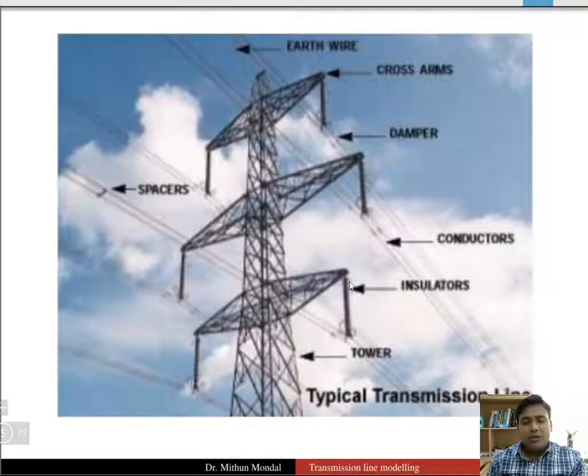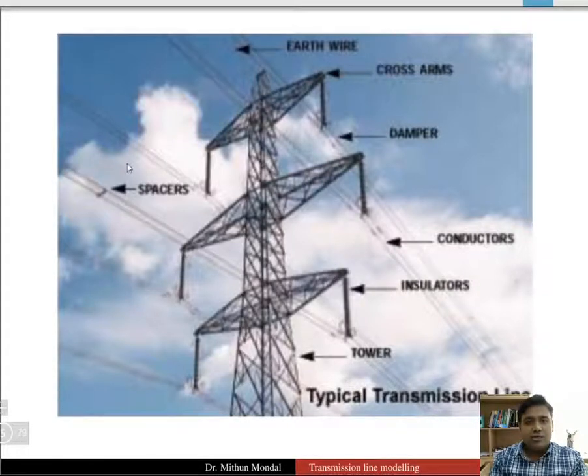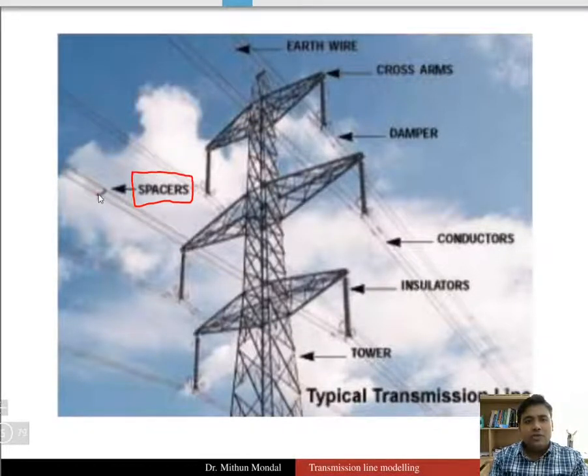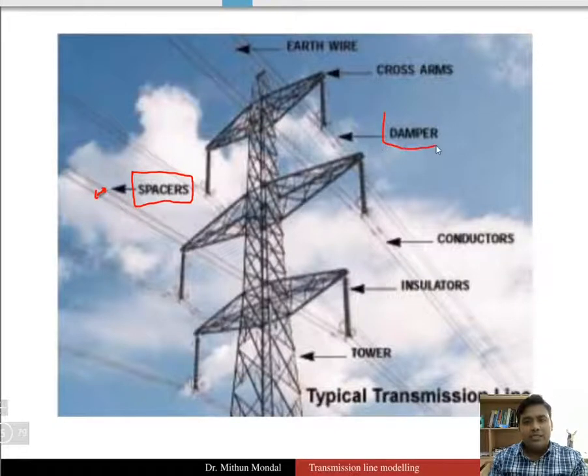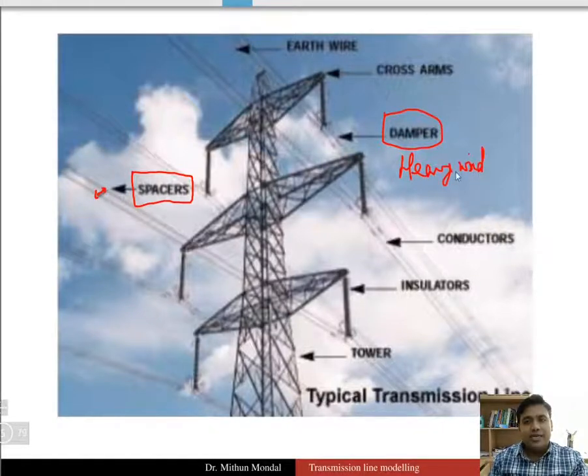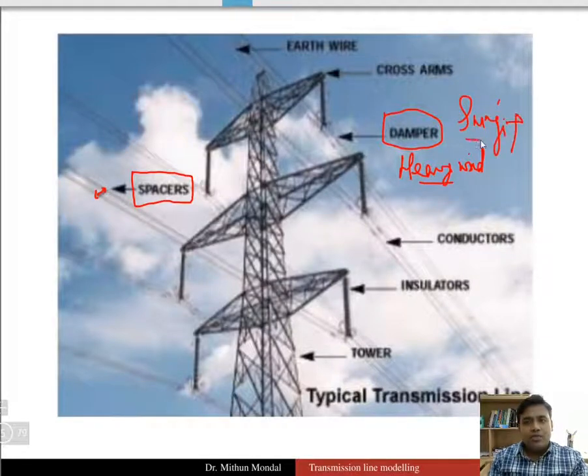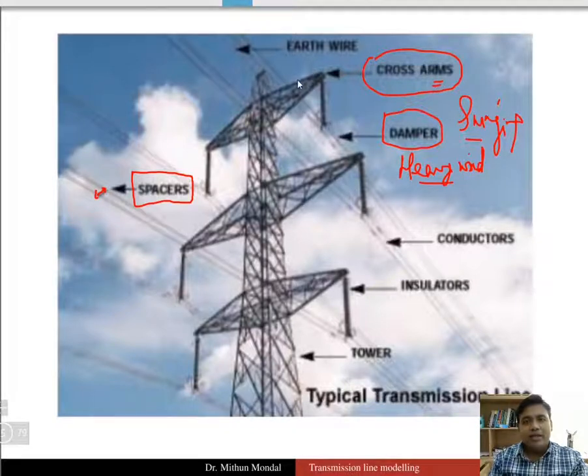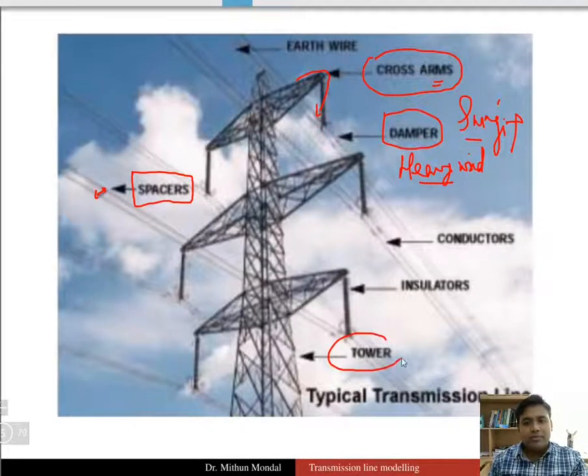Various devices are used to prevent faults in the transmission line. Spacers keep two transmission line conductors at a distance. Dampers are used when there is heavy wind — they avoid the swinging of the conductor. Cross arms help protect conductors from touching each other when there is a bend in the conductor. The tower itself can be of various materials: wooden, concrete, or steel.